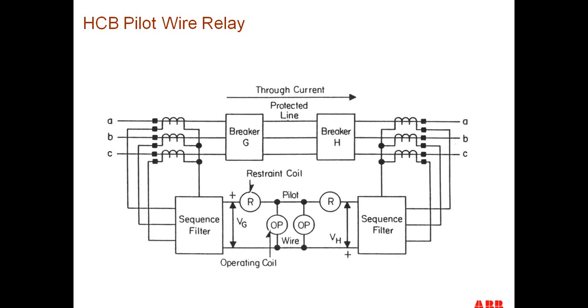When we had an internal fault, then the respective polarity of VH to VG would reverse with respect to each other, and so we would get no circulating current, but all current would go through the operating winding, and the relay would operate. It's a very, very simple relay. Actually, the relay was made for a long time, and it's still being applied in several locations.